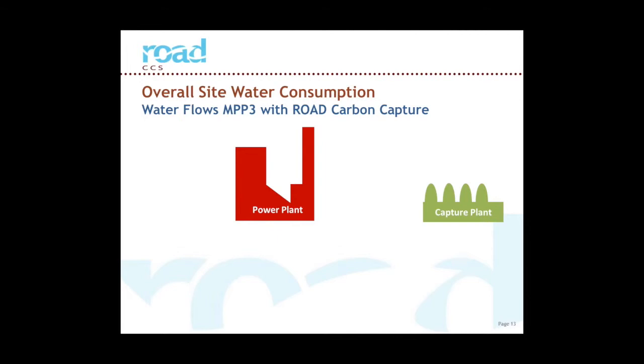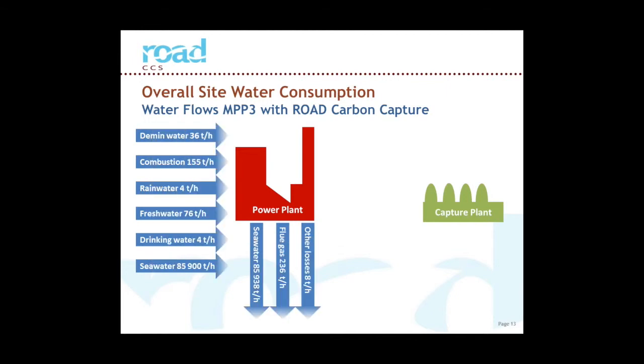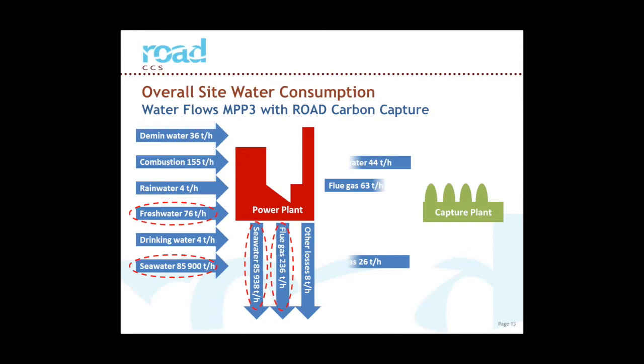Those are the charts you've seen before, but some of them have changed. The ones with the red circles have changed now. The freshwater consumption has fallen, and that's because we've added direct contact cooling water into the FGD. So this was 120, it's fallen by 44 tonnes an hour because the condensate that we're condensing in the DCC is replacing that fresh water.